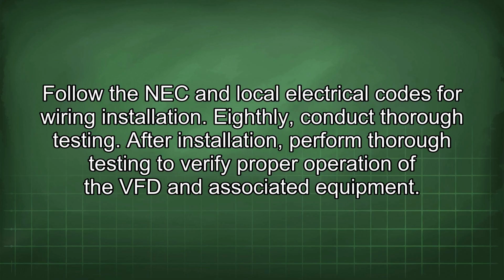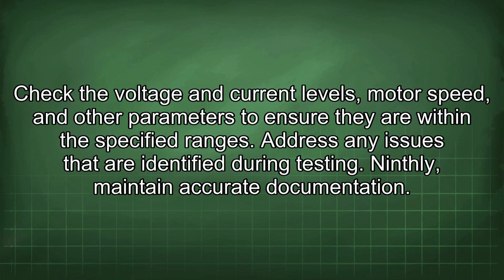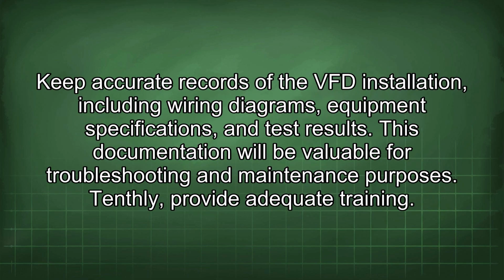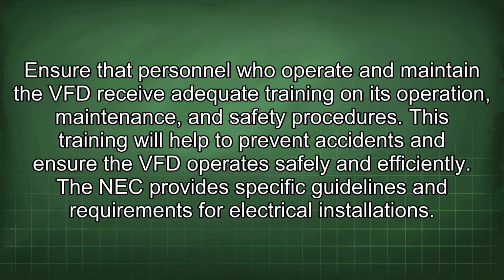Eighthly, conduct thorough testing. After installation, perform thorough testing to verify proper operation of the VFD and associated equipment. Check the voltage and current levels, motor speed, and other parameters to ensure they are within the specified ranges. Address any issues that are identified during testing. Ninthly, maintain accurate documentation. Keep accurate records of the VFD installation, including wiring diagrams, equipment specifications, and test results. This documentation will be valuable for troubleshooting and maintenance purposes. Tenthly, provide adequate training. Ensure that personnel who operate and maintain the VFD receive adequate training on its operation, maintenance, and safety procedures. This training will help to prevent accidents and ensure the VFD operates safely and efficiently.